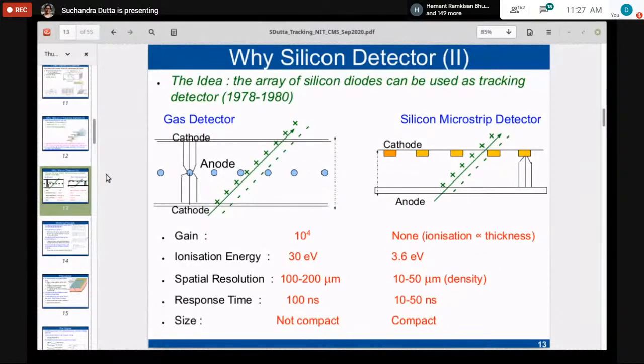You see the difference. Then we have the spatial resolution, which is on the order of a few hundred microns, as I already said, and here it is 10 to 50 micron, depending on the density of the material chosen. And the size, because in the case of a gas detector we need a large volume, whereas the solid state detector can be very compact. So these are the advantages which came into the picture, and the very good spatial resolution basically dominated the usage of solid state devices.